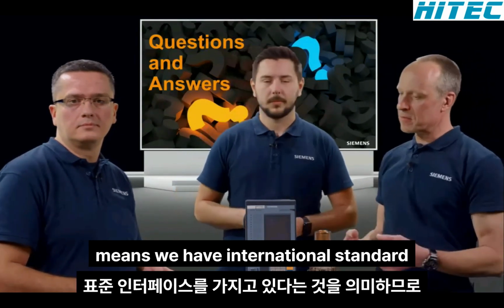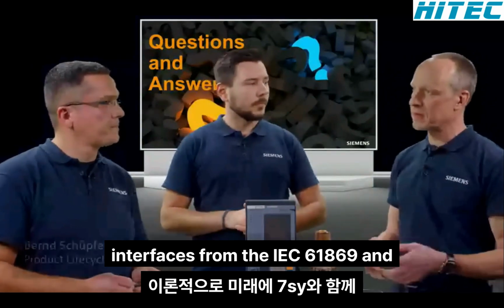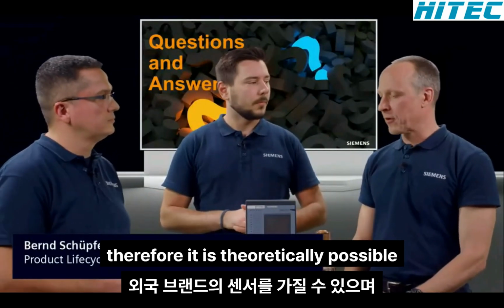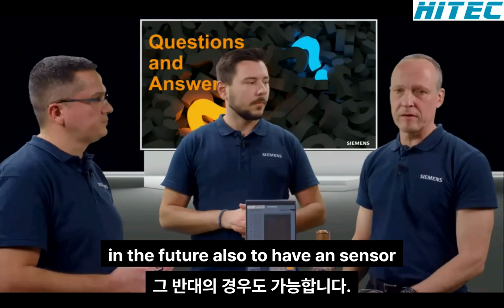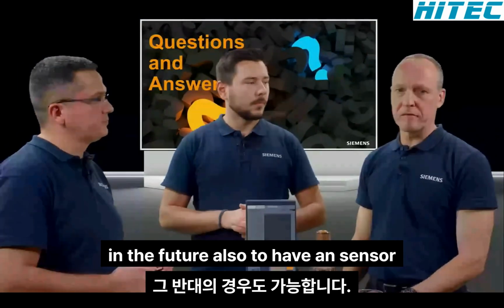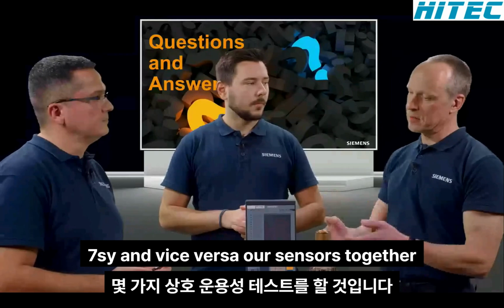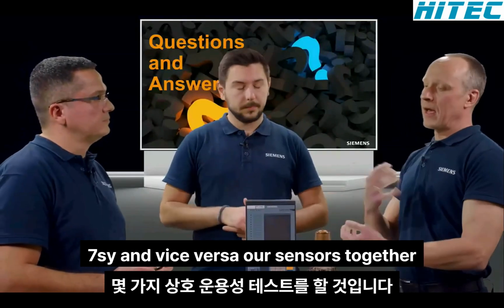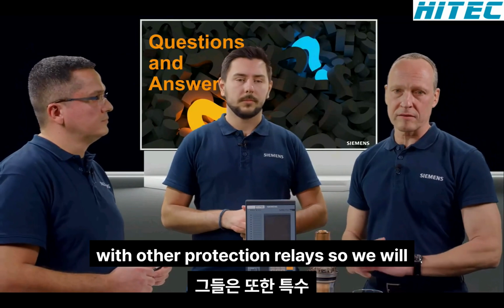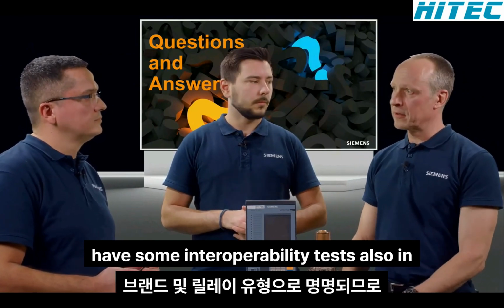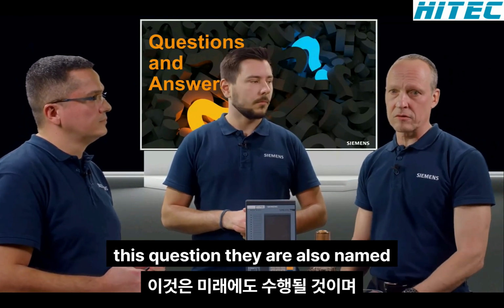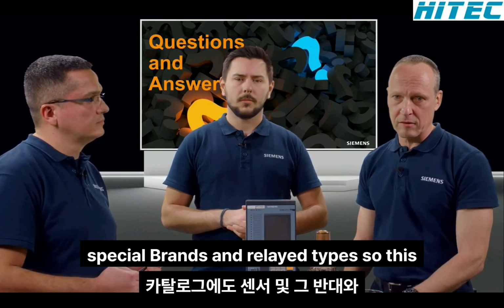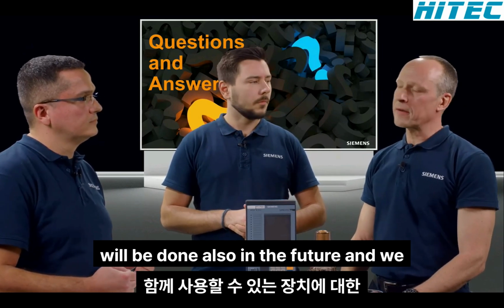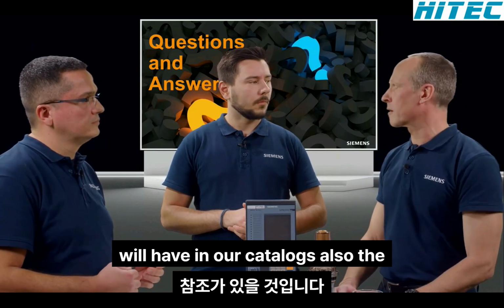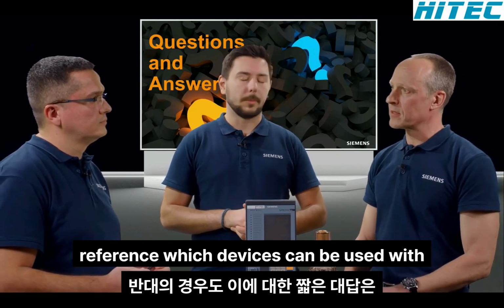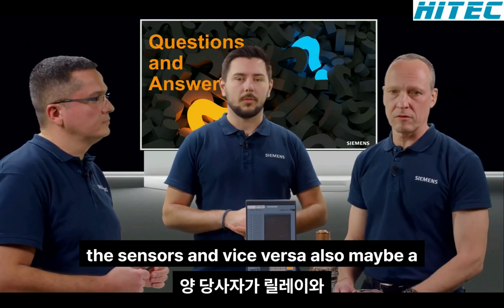That means we have international standard interfaces from the IEC 61869. Therefore, it is theoretically possible in the future to have a sensor from a foreign brand together with the 7SY, and vice versa, our sensors together with other protection relays. So we will have some interoperability tests also. In this question, special brands and relay types are named. This will be done in the future, and we will have in our catalogs the reference which devices can be used with the sensors and vice versa.